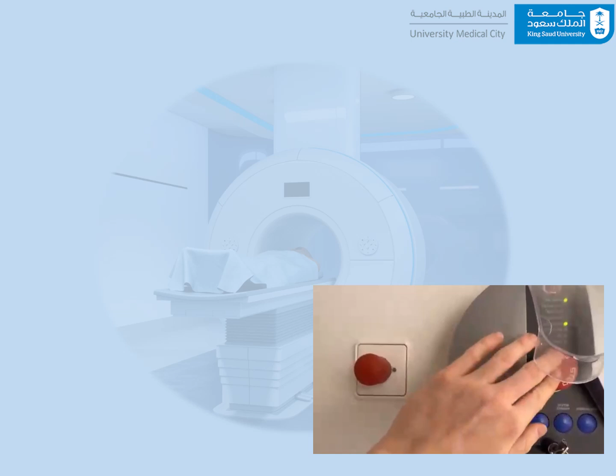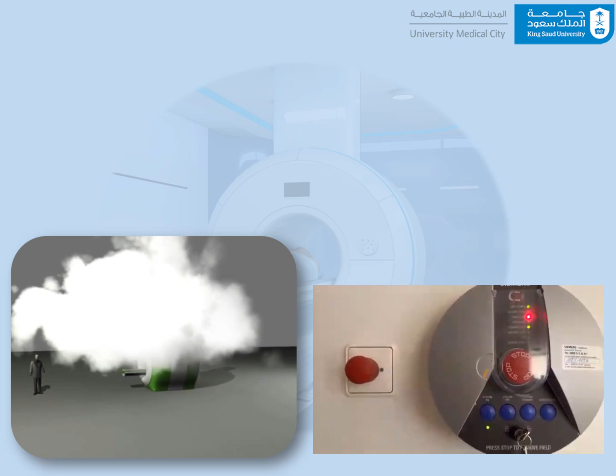When the magnet is quenched, the superconductivity in the electromagnet is deliberately broken down, causing the powerful magnetic field to dissipate rapidly, within around 20 seconds. This is an emergency shutdown procedure that removes the magnetic field as quickly as possible to mitigate the danger. This should only be activated in extreme emergency situations as it might permanently damage the scanner's magnet.